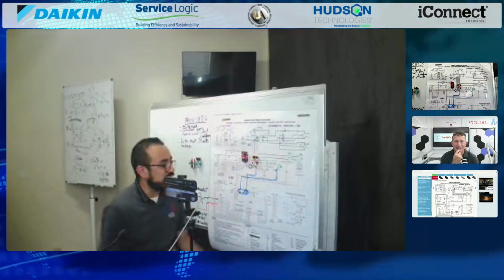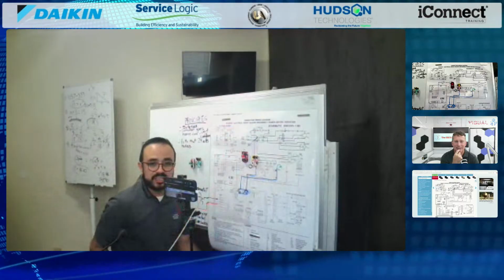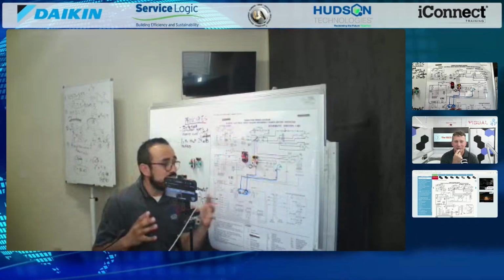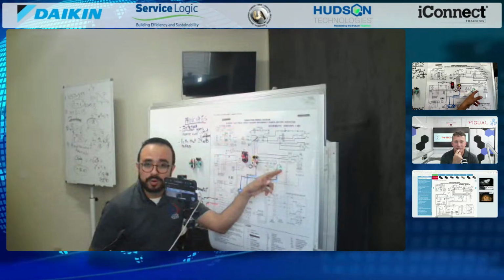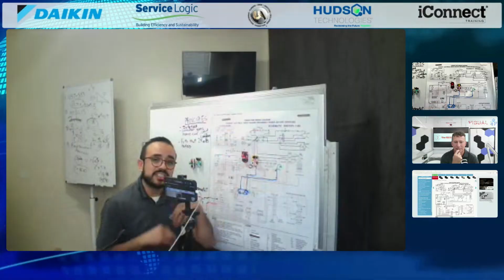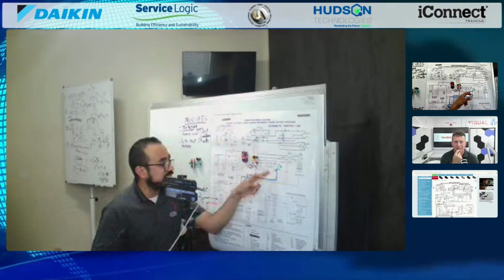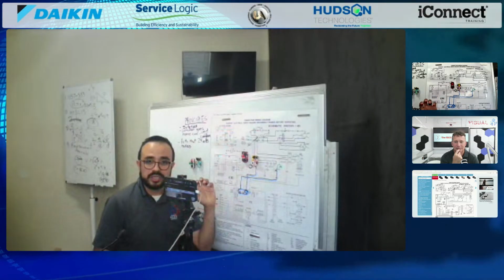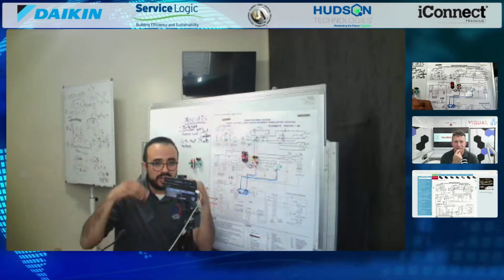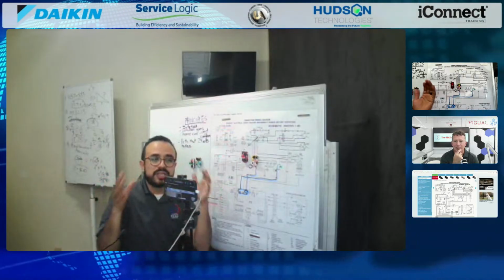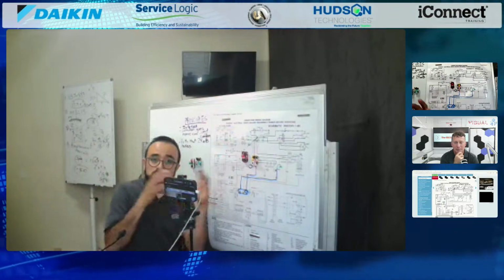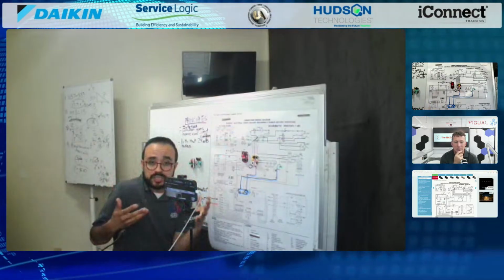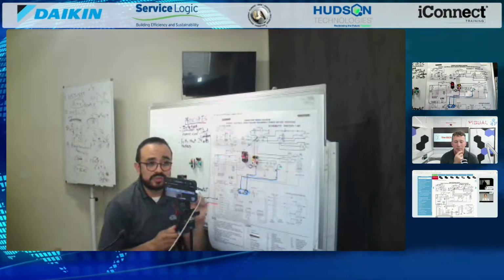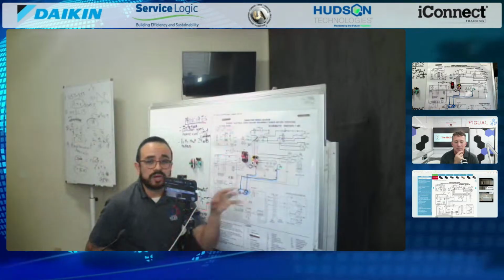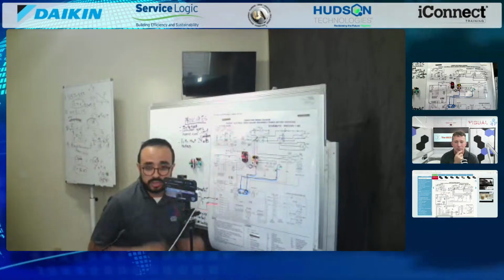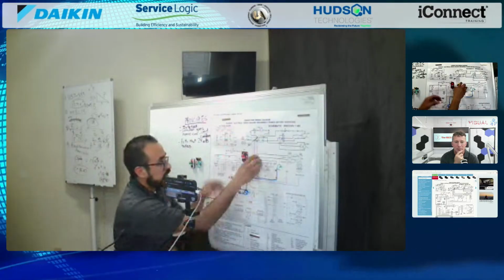That's why I mentioned common—your unit is common, because you need to ground the common part of the transformer. So Mario can't touch the unit, or anything that has common to it. This helps with troubleshooting. I see a lot of old units that do not have their common grounded, and if you did ground it, that will help you with troubleshooting, because maybe you have 24 volts touching somewhere, like the liquid line or somewhere along the unit. So they should always be grounded. That's the whole point.